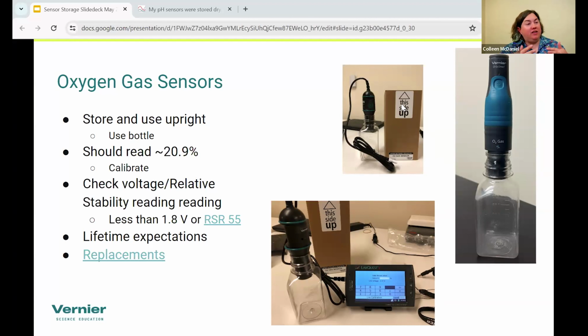The oxygen gas sensor should be reading around 20.9% atmospheric oxygen, depending on your altitude. I should say that does vary. And it's another one of those sensors that's kind of like a pH sensor in that it has more of a defined lifespan. It's not going to last forever. But what's nice about it is that it is refurbishable. So we can actually replace the cell inside of it and get it up and running functional for you again without you having to buy a whole new sensor.